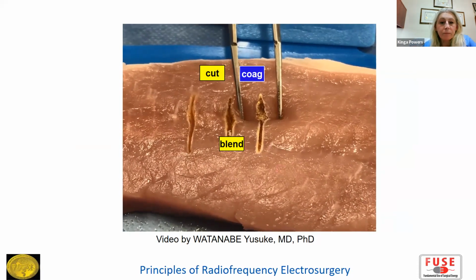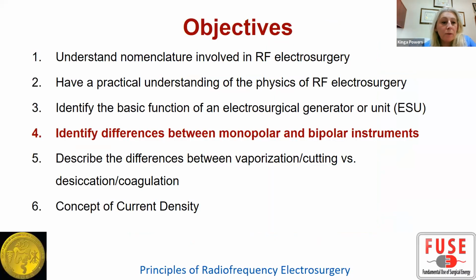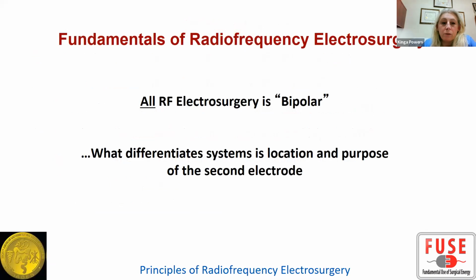Next we're going to talk about differences between monopolar and bipolar instruments. Basically, you can think of all electrosurgery as bipolar because there are always two electrodes. What differentiates monopolar from bipolar is actually the location of these two electrodes.